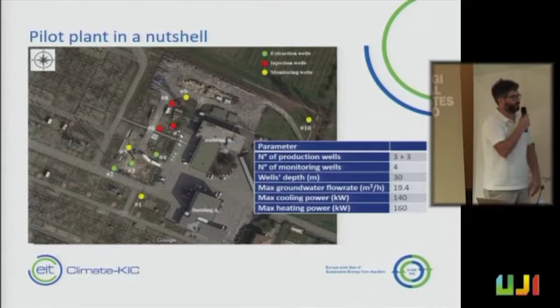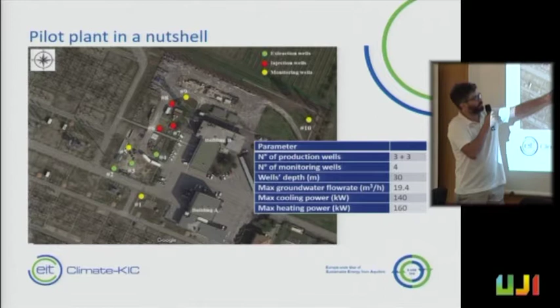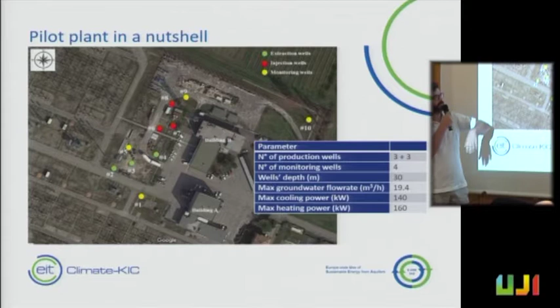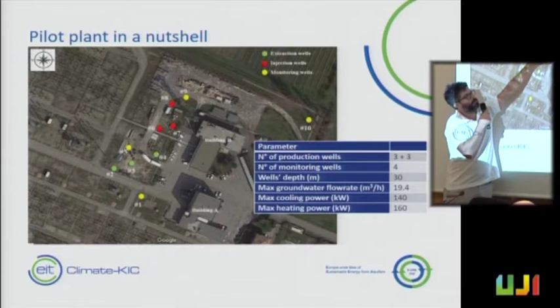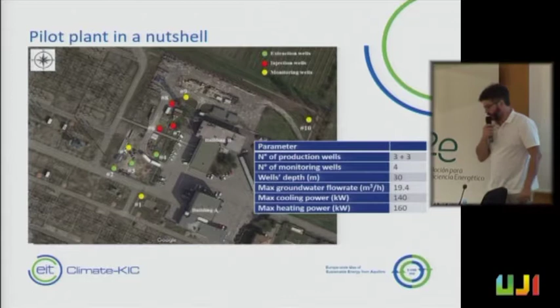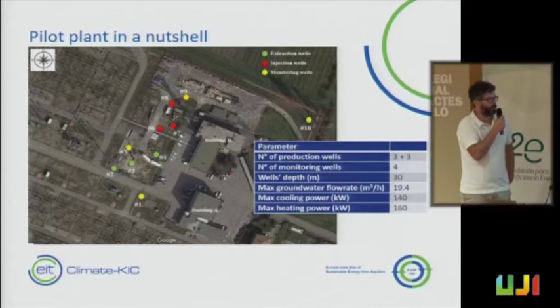We have several wells. The yellow ones are monitoring wells, used only to measure the temperature of the aquifer and the level of the aquifer. These three are extraction wells, so from these wells we pump the water from the groundwater, send it to a technical station where there is a heat exchange between a primary circuit and a secondary circuit. They take the heat or the cool to the buildings, and then we reinject the groundwater in these red injection wells. So we have 6 production wells - 3 for extraction and 3 for injection - and 4 monitoring wells.